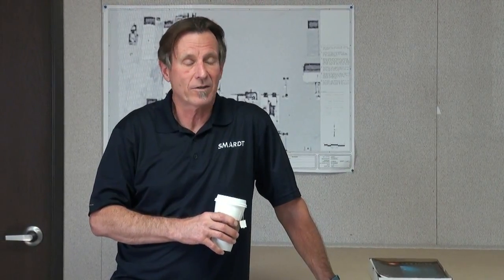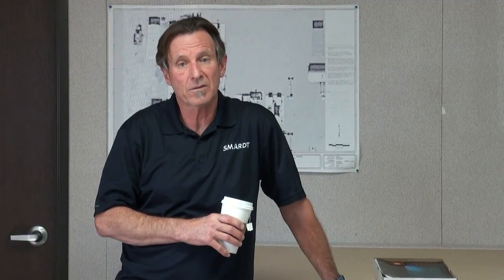Any centrifugal compressor doesn't like high lift situations. They go into a surge, which is reverse flow through the compressor. Is that destructive to these? No, not necessarily. I imagine it'd be destructive if it was really severe for a very long time.